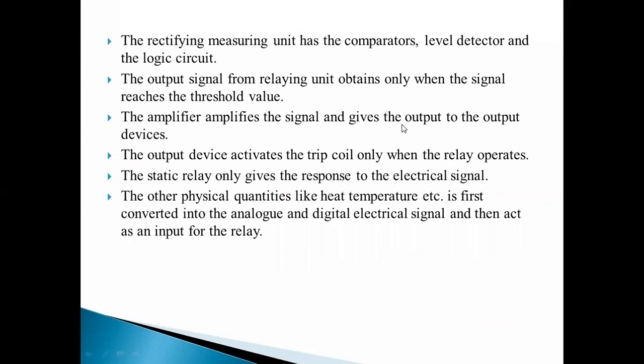First, this rectifying measuring unit has the comparators, level detectors, and the logic circuit. The output signal from the relaying unit is obtained only when the signal reaches the threshold value. Threshold value means your pickup value. When it exceeds that value, then only your relay will actuate. When that relay operates, the signal will be given to the circuit breaker.